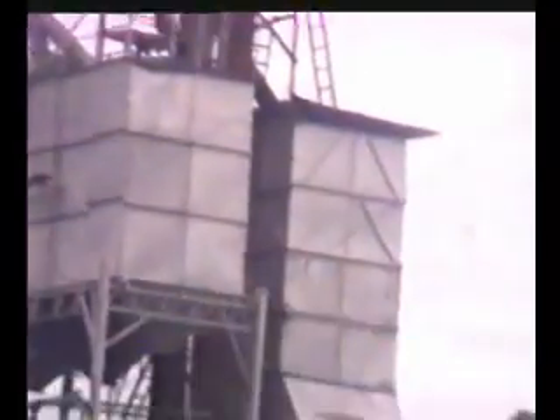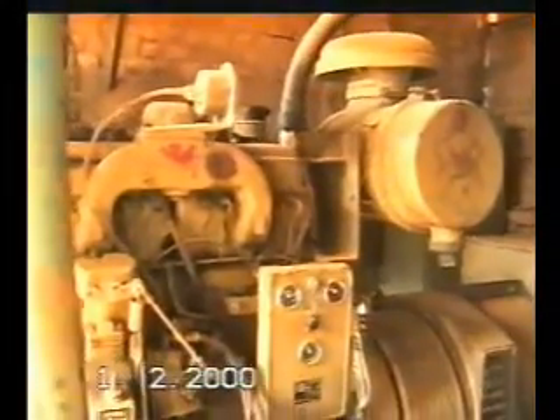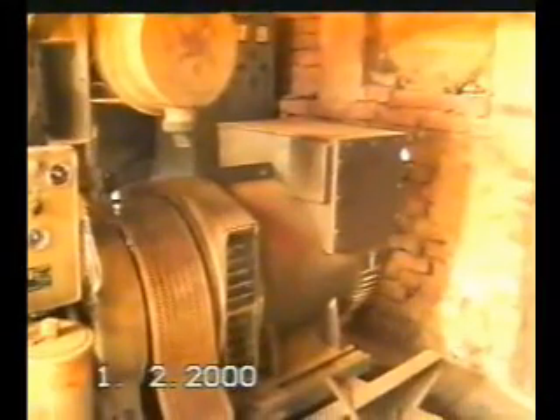The producer gas can also be used for the generation of thermal energy. To see that, we are now at the Bijay Lakshmi rice mill, Midnapur, West Bengal. The gas line from the gasification plant has been divided into 3 branch connections. One has gone to this 125 kVA DG set. The existing DG set has been retrofitted to run on dual fuel with producer gas to generate the entire captive power. The power generated has made the grid connection redundant.